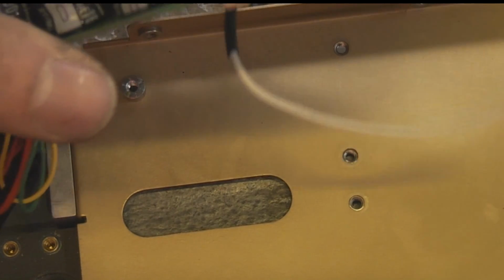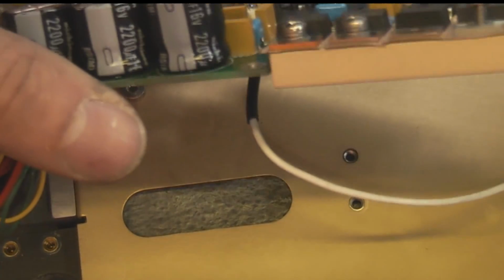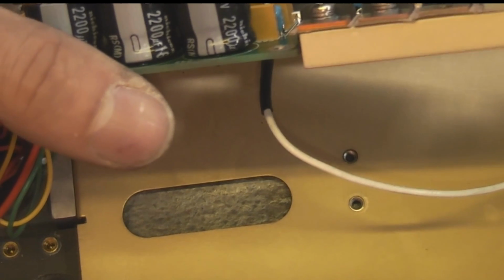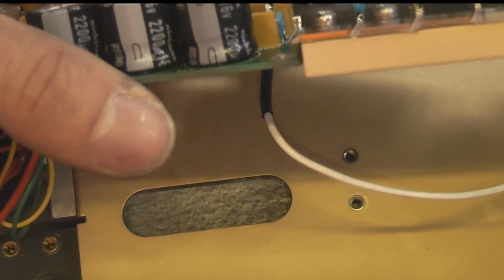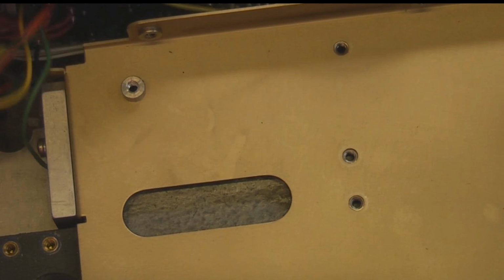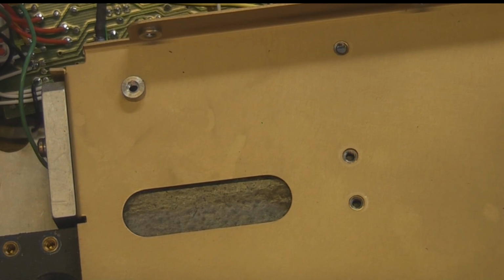The way that X-ray tubes are typically regulated is they have a constant voltage supply, then they adjust the filament current to get the required beam current, because the voltage provides the characteristic spectrum of the X-ray, so you want that to be constant. So the only way to adjust the current is then adjust the emission of the filament, although again, because these have got an electron gun, there might be other ways they can do it via controlling some of the electrodes on the electron gun as well. Don't know enough about the electron physics to know exactly what they do here.